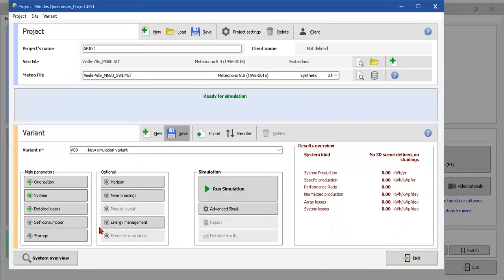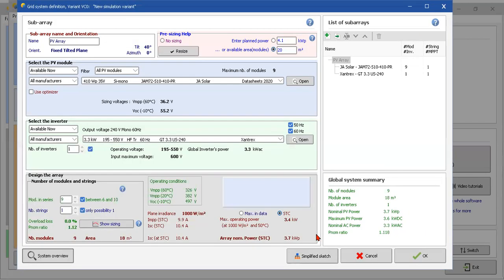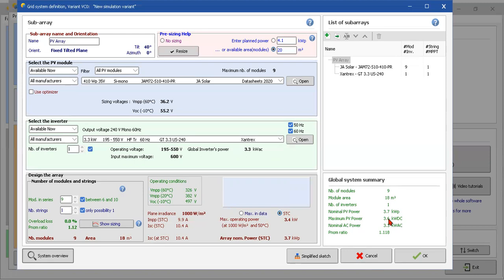We're gonna put okay. There's something important here. I just put in System again to show something. Here - nominal PV power. This is the maximum power that we're gonna produce. And this is the maximum PV power that we're gonna use - 3.6 kilowatts. Okay, in DC. And we're gonna produce in AC 3.3.